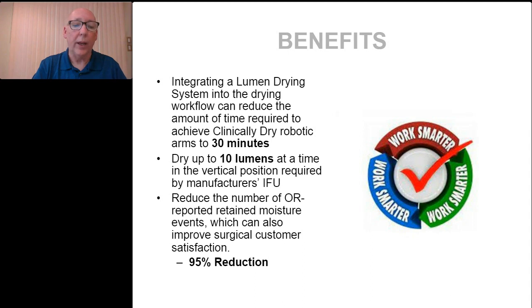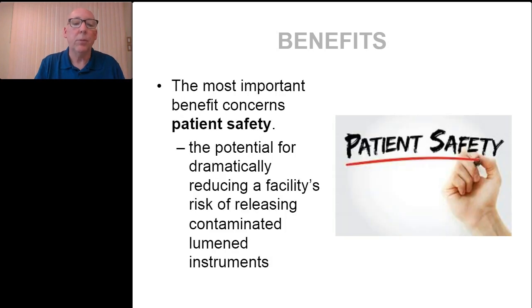As well, they can dry up to 10 lumens at a time and reduce the number of OR reported retained moisture events, which can also improve surgical customer satisfaction. There was a 95% reduction in the number of OR reported retained moisture events through this study. The most important benefit, obviously, is patient safety, the potential for dramatically reducing a facility's risk of releasing contaminated lumen instruments.